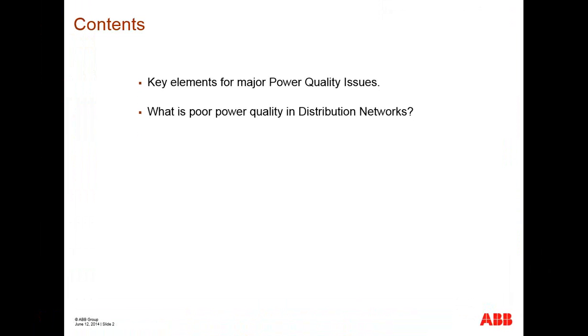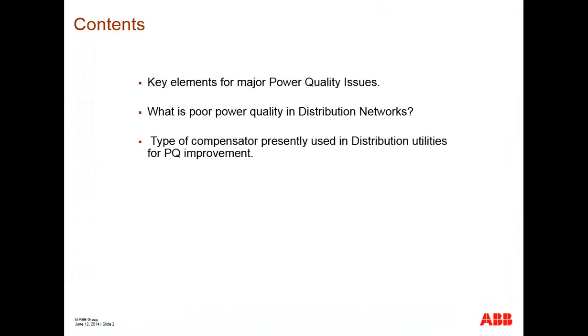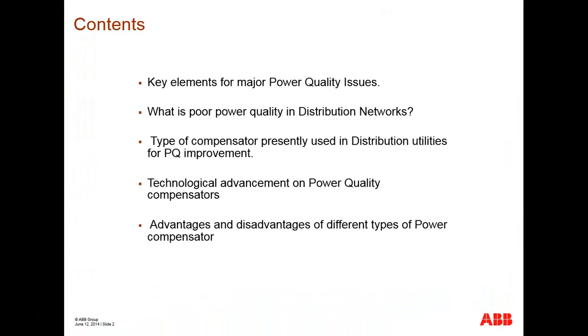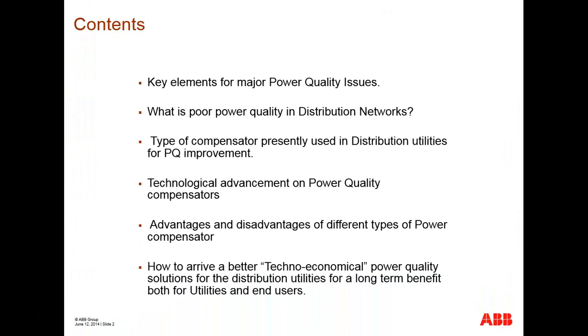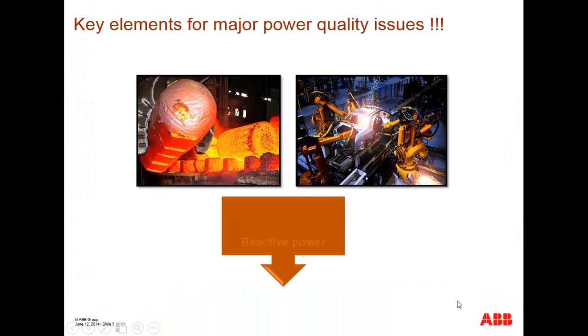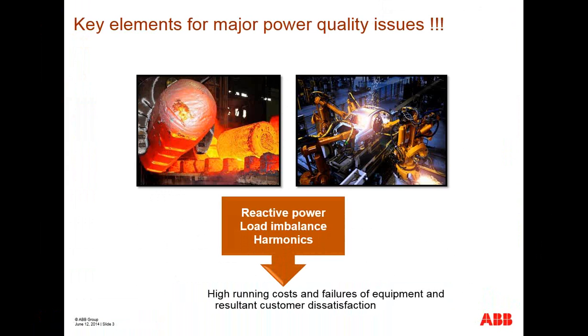So as I explained, the content is: key elements of power quality, what is poor power quality in the distribution network, type of compensator, technical advancement in the power quality field, advantages and disadvantages of the power quality compensator, and a techno-economical solution which will be beneficial both for the utilities as well as for the end user. The major issues, as I explained, are basically because of three issues, related to reactive power, load unbalance, and harmonics. And this is causing high running cost or failure of equipment and resultant customer dissatisfaction.